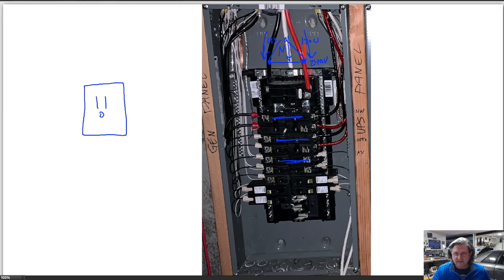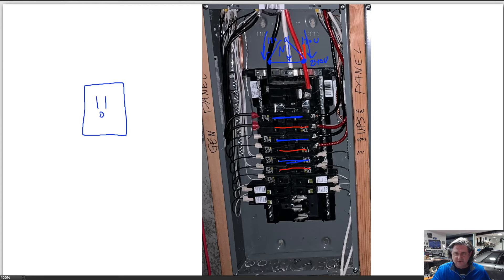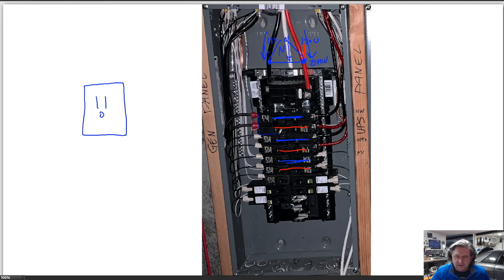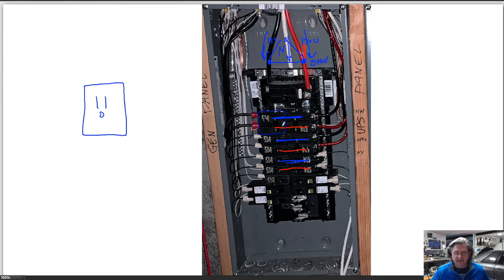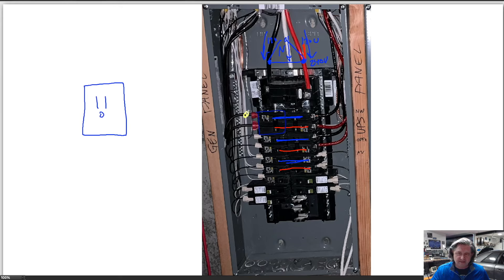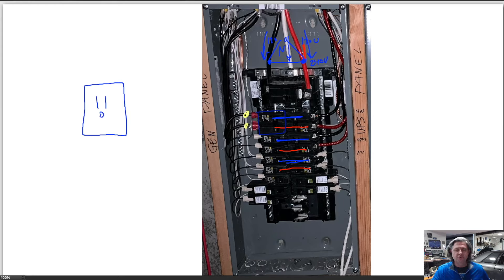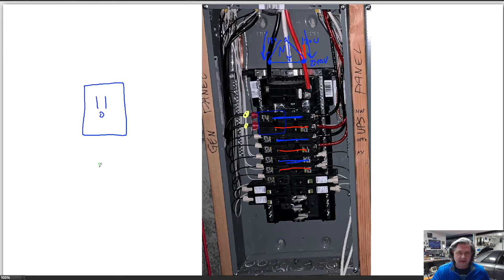The reason this is done is that then if you put a breaker, and these breakers can go on one side or the other, that has two breakers, it's attached to both the A and B leg. What that means is that then you can hook up a device to both of those two wires, that's 240 volts.